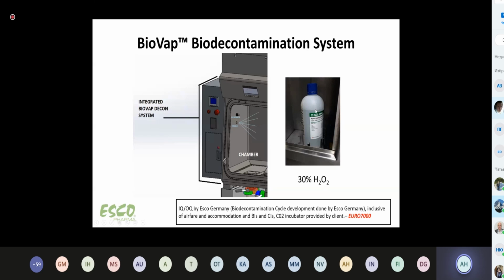So when the bottle is used, the chemical becomes less and less, then it can alarm to the customer via the HMI to say, okay, customer, please replace the H2O2. And this is how you actually spray the H2O2 into the chamber. Again, I repeat, you have here the gassing for one chamber or 2 chambers. You can choose via the HMI.